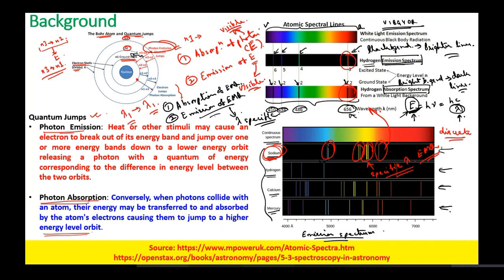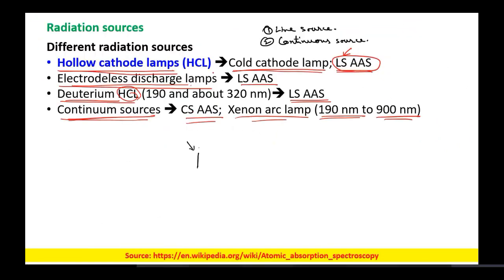If you want to excite a sodium sample — to find out whether there is any sodium element — you will generate light of the sodium metal, which generates specific wavelength light that can be used to stimulate only and only the sodium ions. This is what hollow cathode lamps do — they generate specific wavelength electromagnetic radiations capable of exciting the target samples.